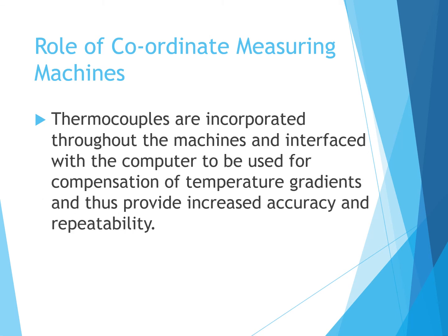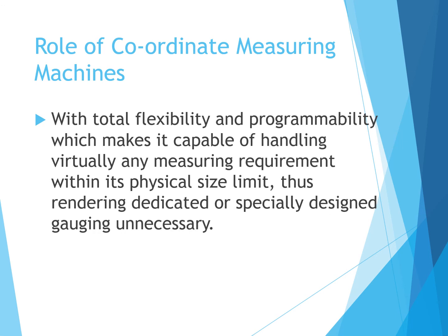Then these CMMs have thermocouples. There are thermocouples incorporated throughout the machines and interfaced with the computers to be used for compensation of temperature gradients, and thus provide high accuracy and repeatability. So you can get high accuracy and repeatability, for which you are using these thermocouples.